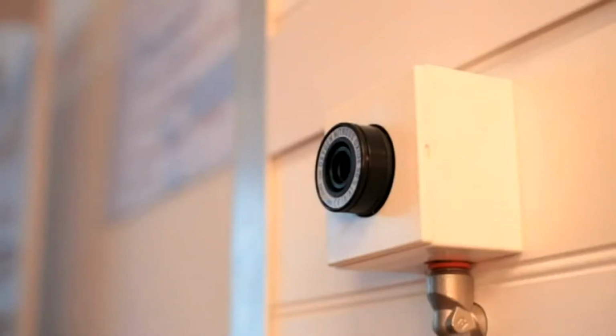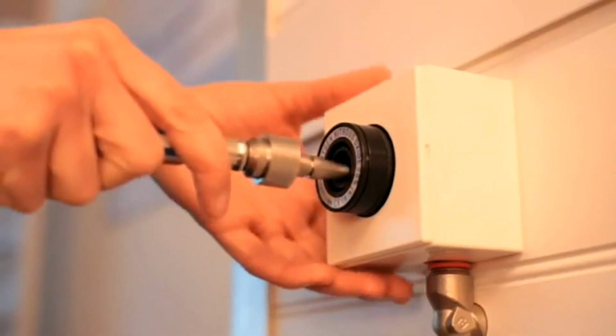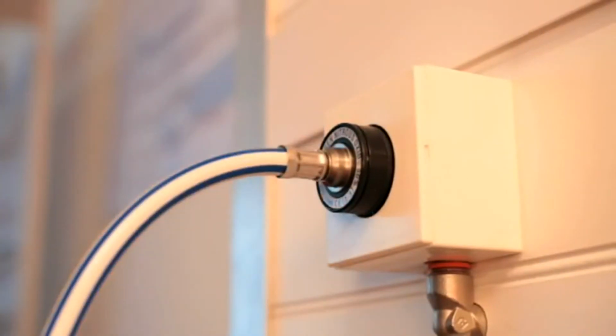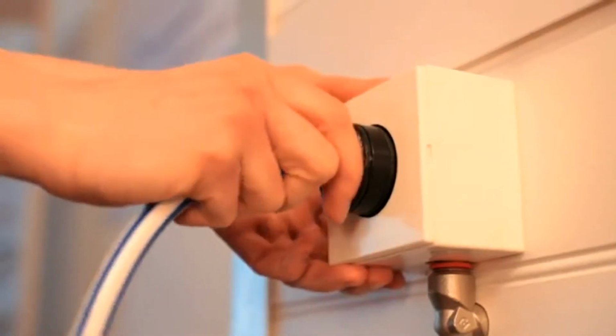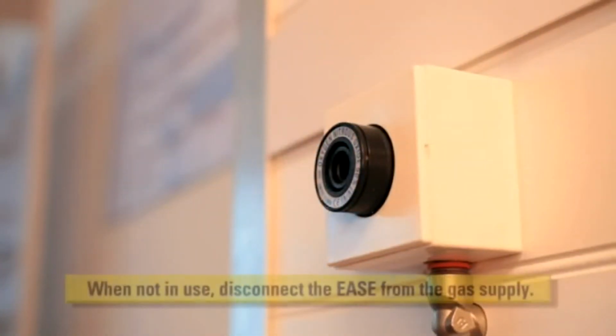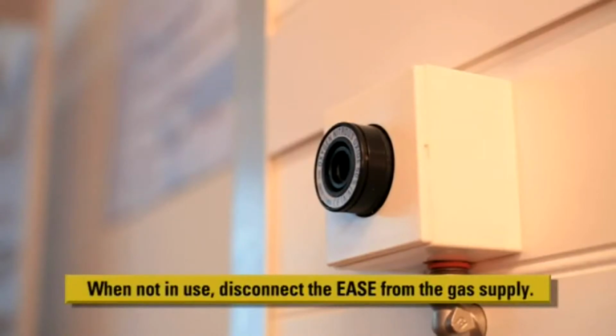Ease demand valves with BS5682 probes can be connected to a wall terminal by pushing the probe into the terminal outlet. To disconnect from the wall terminal, push back the outer collar and withdraw the probe. When not in use, disconnect the Ease from the gas supply.